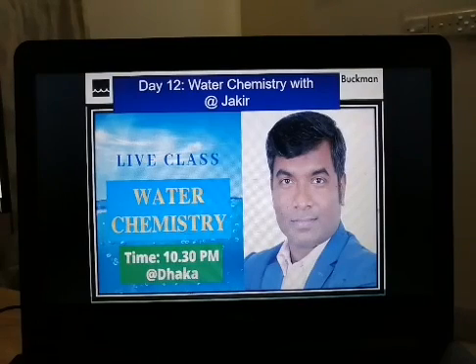Kumar Bandi, thank you very much. Sodium sulfite is used as oxygen scavenger for low pressure boilers. It can be used only for low pressure, and the pressure can be maximum 20 kg. You can't use sodium sulfite as an oxygen scavenger above 20 kg.